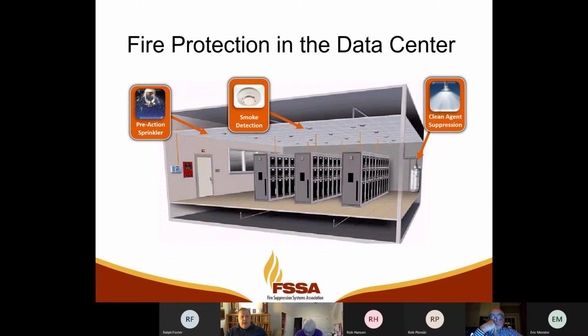So, in fire protection, there's really three systems that aisle containment systems can affect. Sprinkler systems, clean agent like FM200, Novec, or Sapphire, or whatever clean agent system you may have, gaseous systems, they can be affected, and smoke detection. Those are the three systems that are primarily affected by aisle containment systems if they're added to the data center and these other systems are not addressed because of that.